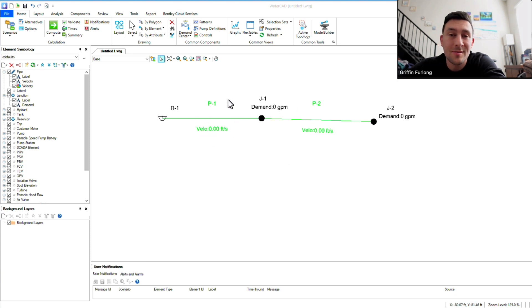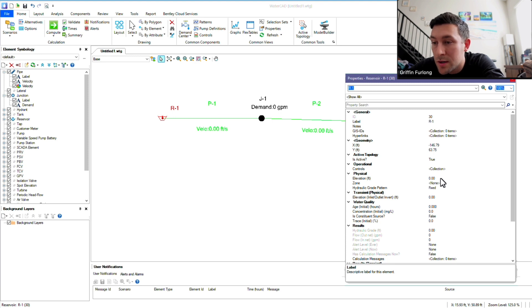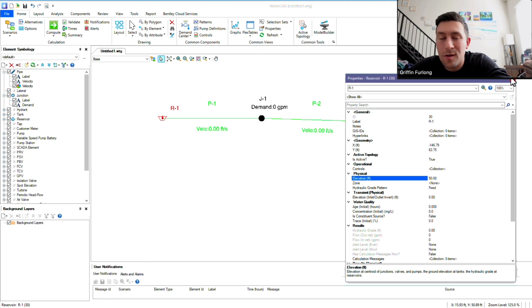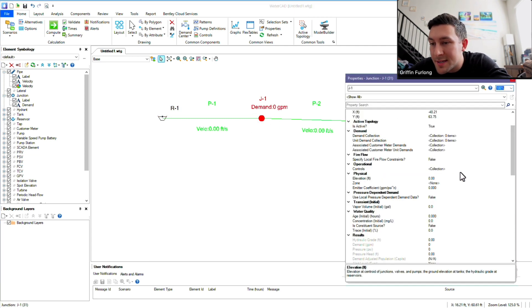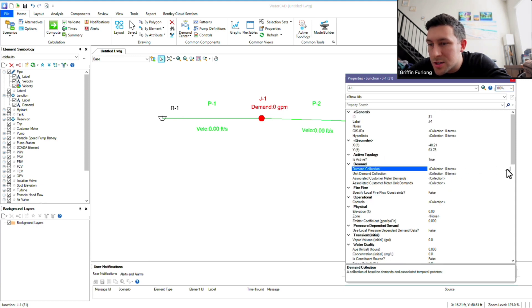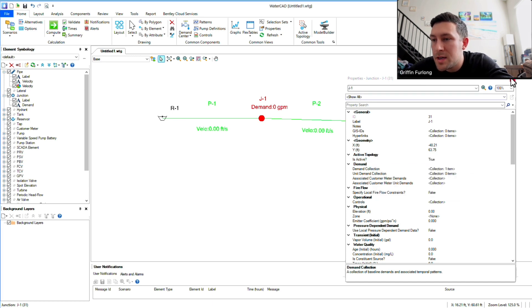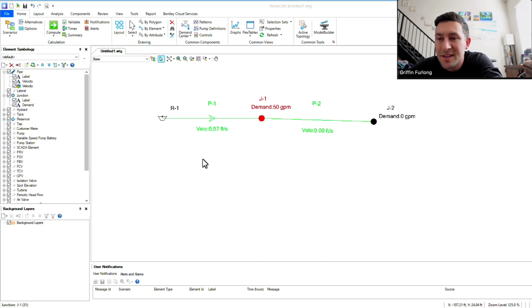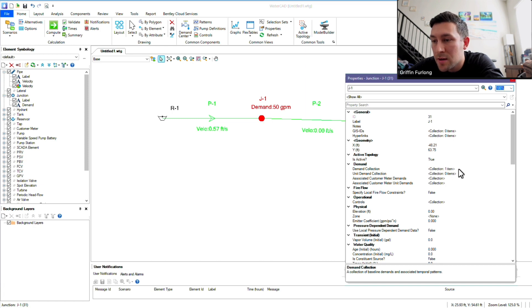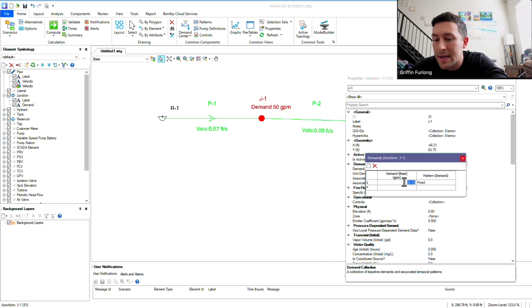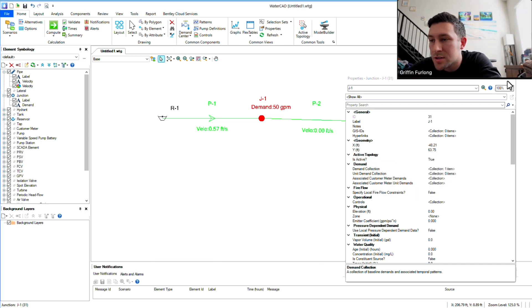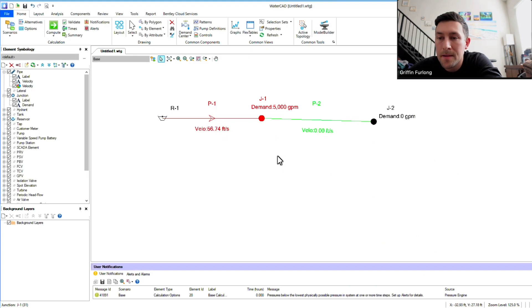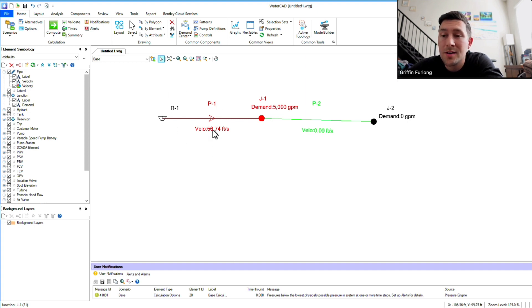This is showing that we're green, which is good because we wanted to be below the 5 FPS threshold. So if we go in here and start setting some elevations of the reservoirs — let's set this to 50 — and add some demand. We have a demand collection, so let's input a demand. Let's go 50 GPM through that junction. Let's go ahead and compute. We're still actually pretty good here — our velocity is not even reaching over 5 FPS. But you see the point: we've created some nice annotative and color codes to really help us analyze our design. If I were to put a whole bunch of flow into this system — let's compute again — voila! In that pipe we got 5000 GPM going to that node, and we got a velocity well over 5 FPS, so that's why it has signaled red.